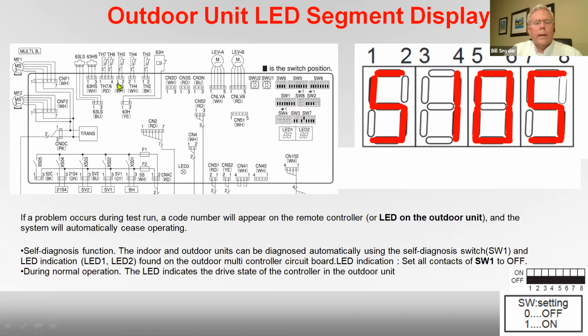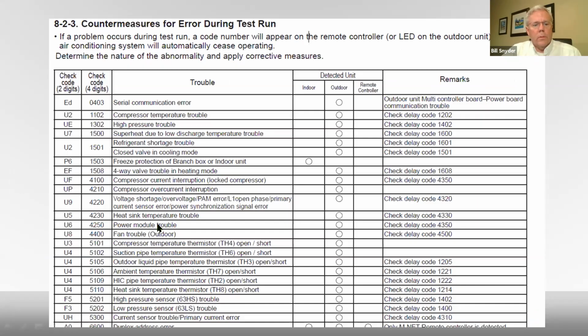So I would pull that out, take your own meter in there and see if it's open or shorted. If it is, replace the thermistor or find where the wire is bad and try to repair it, at least temporarily. I would always replace it, because just twisting wires together with a wire nut is probably not the best. You might get by for a few days, but order the right thermistor. Okay, that's one thing you can do.